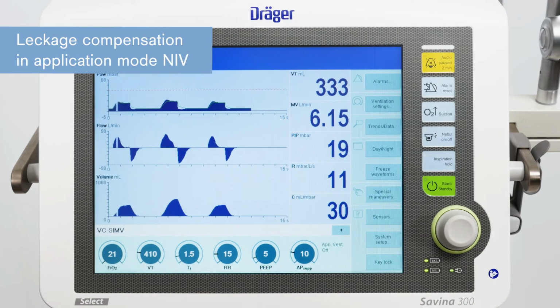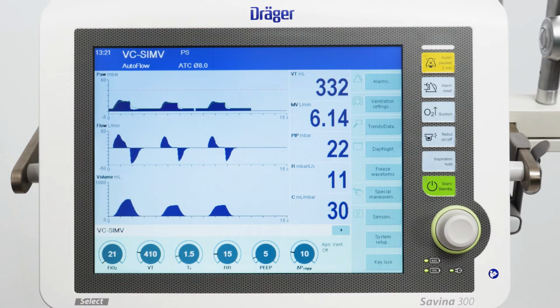Leakages are greater with non-invasive ventilation than with invasive ventilation. Savina 300 Select takes into account the leakages in the NIV application mode accordingly. The inspiratory trigger is automatically adapted to the measured leakage. The measured values for tidal volume are leakage corrected and indicate the patient's actual tidal volume.